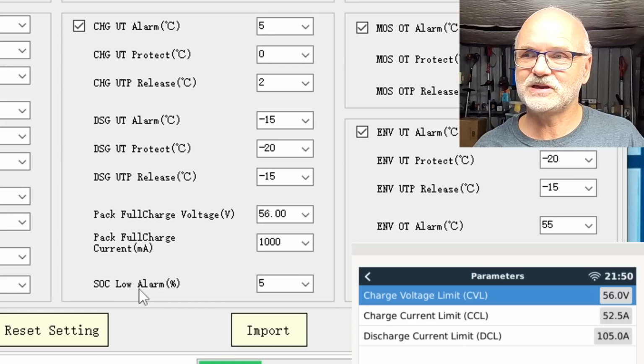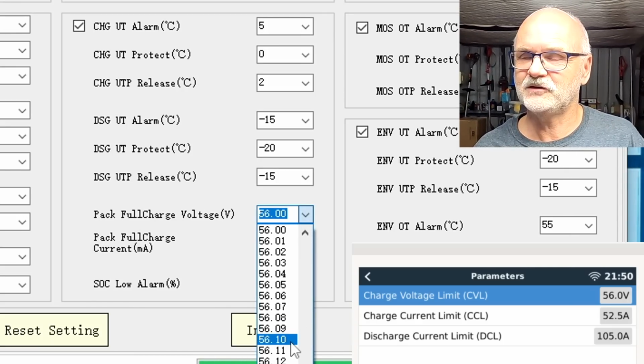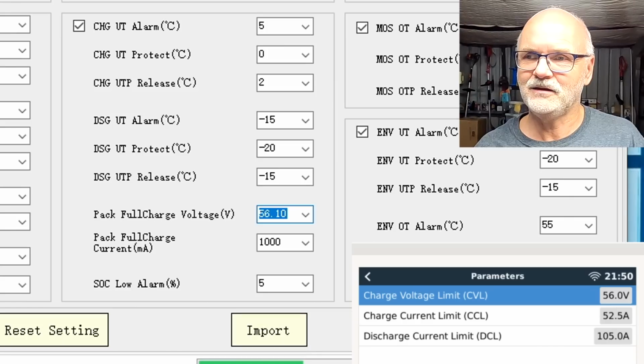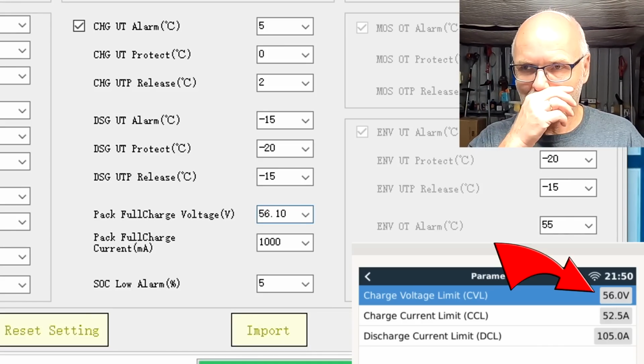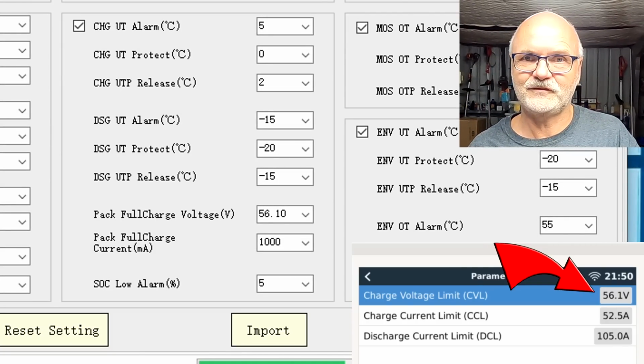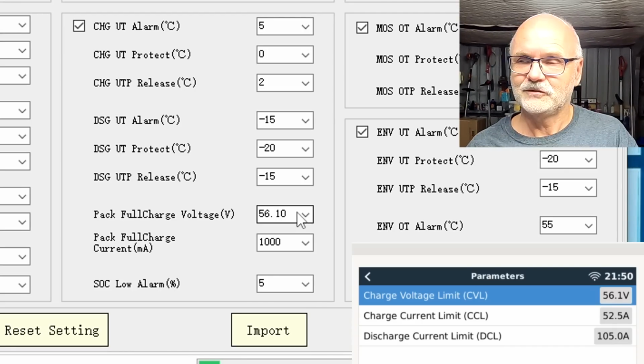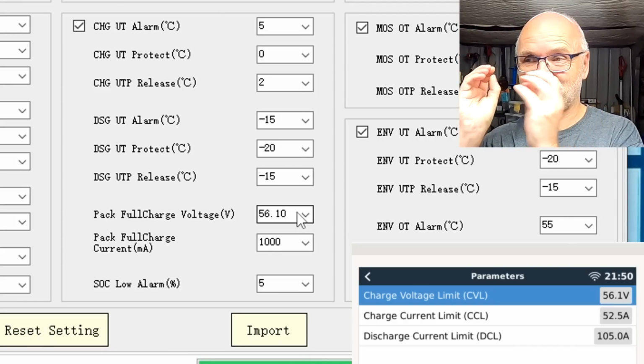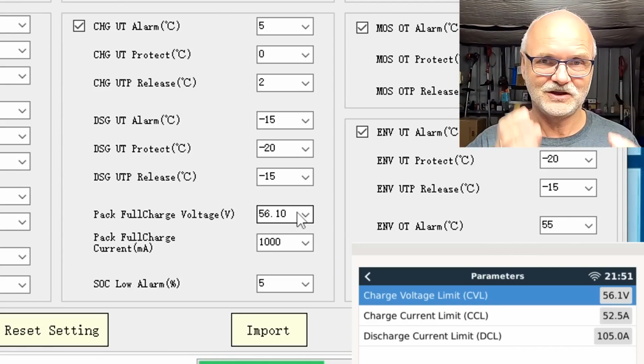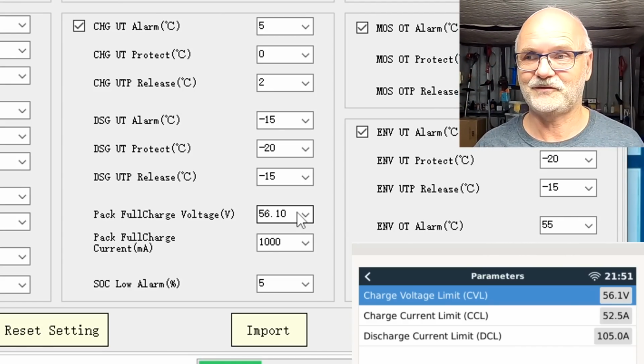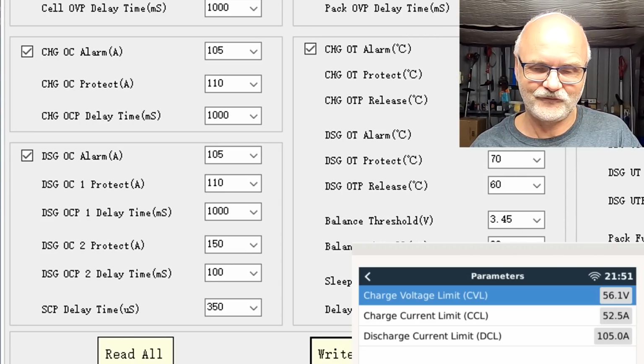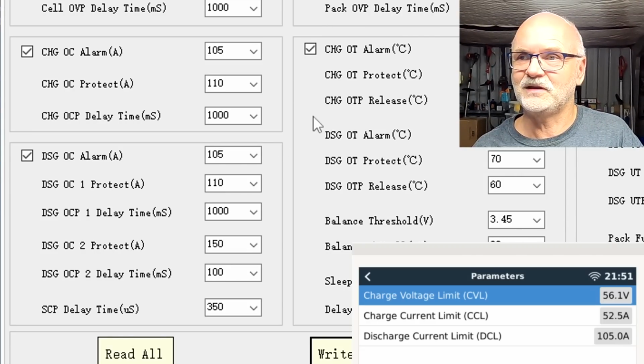The charge voltage limit of 56 volts, that is very easy because this is our Pack FullCharge Voltage. So if I change this one here to 56.10 and write the parameter back to the BMS, you can see in the Victron system it changes to 56.1 as well. So there's no formula here, it is the exact parameter as we set it in the BMS showing in the Victron system. Big plus.